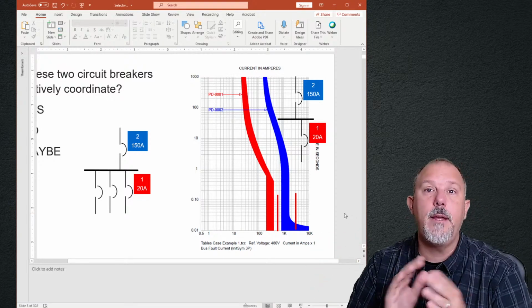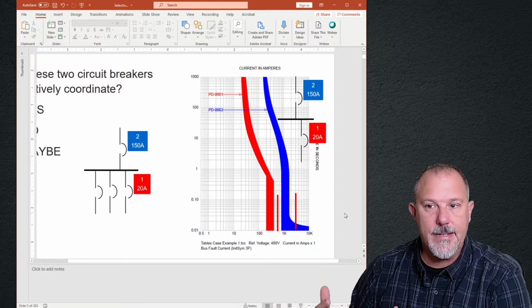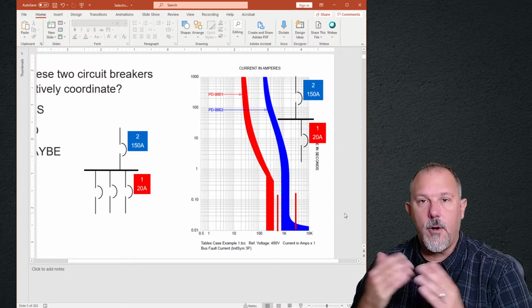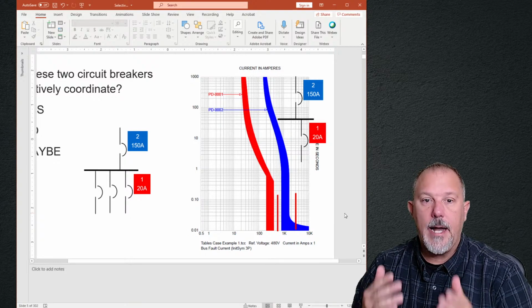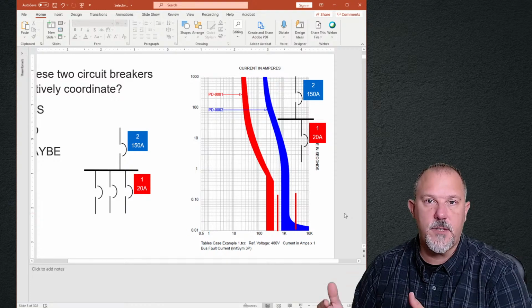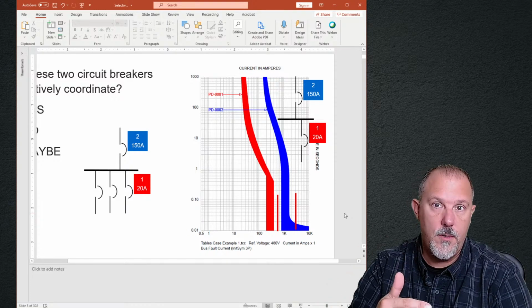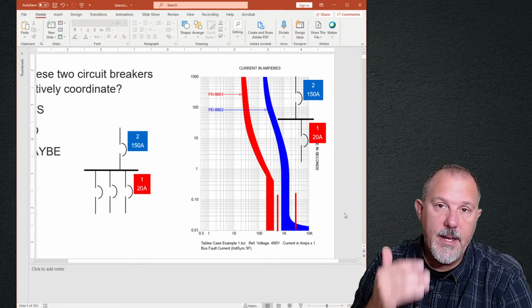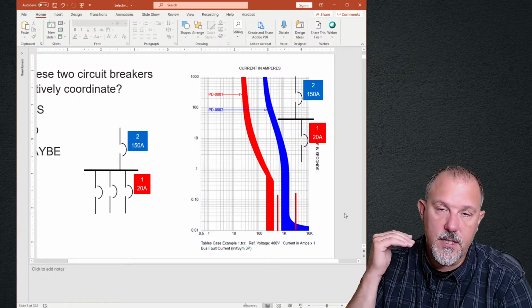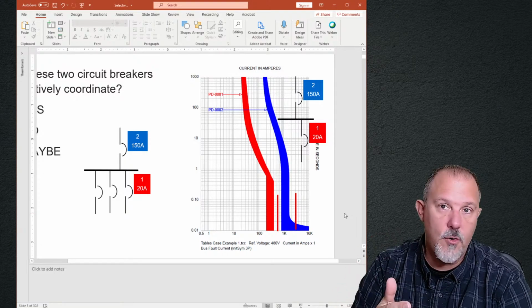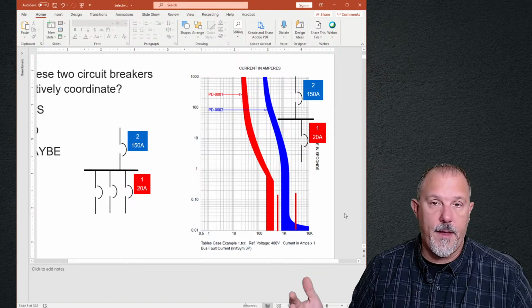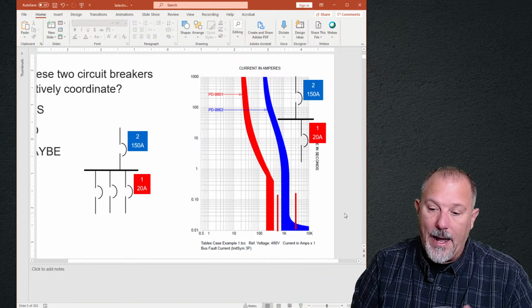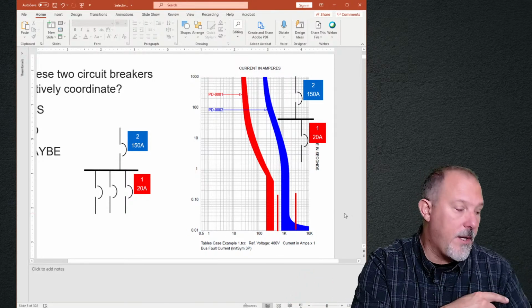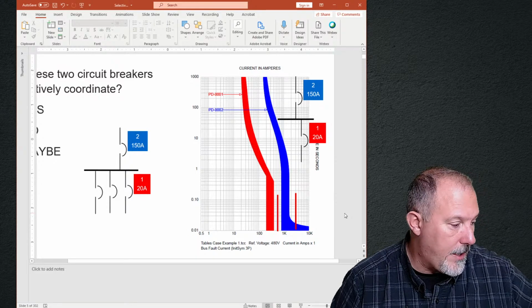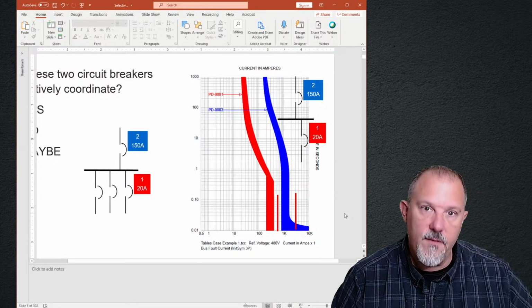I might put in a transformer in my design. Regardless of that, I would have to make adjustments, because I know that for a given fault current value, if it is the three-phase bolted fault current value, they're both going to open. I can't ignore that.